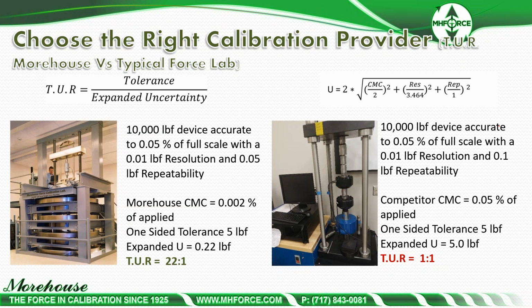So right calibration provider. Here's what you look at things here. You look at the data. 10,000 pound device accurate, 0.05% full scale with a 0.01 resolution and 0.05 pound repeatability. Over here, the machines just aren't going to give you as good of repeatability, but they can get pretty good. But if we look at this, TURs, when we start looking at this ratio, TUR 22-to-1 versus the transfer machine 1-to-1.